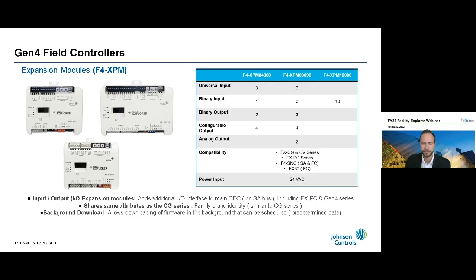It is also important to know that the XPM expansion modules are compatible with all the FX controllers, new and old generation, including the F4 SNC, through the SA bus. They can also be connected to the FX or the FC bus, and are compatible with the FX80 supervisory controllers or the SNC if it's on a supervisory network, and can coexist with either the SA or FC bus.